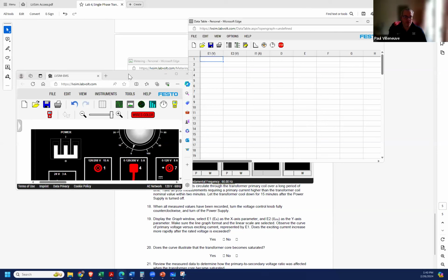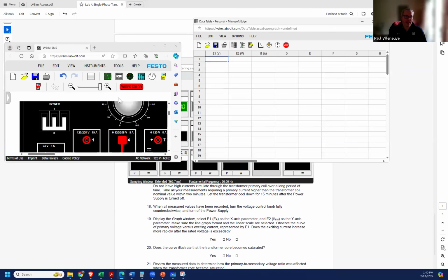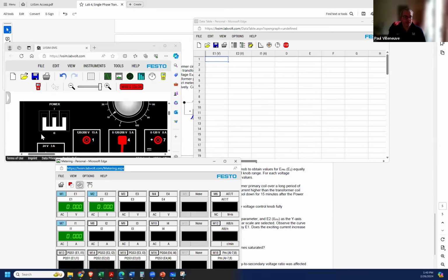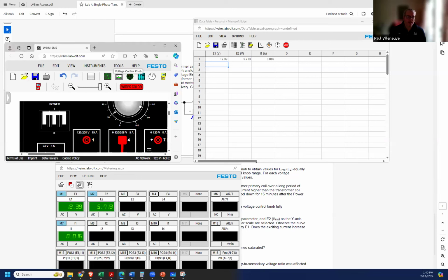The very first point I'm going to take is at 10% voltage—just ballpark, I don't have to be perfect. I'll bring this metering window down here, flip my switch, and record this data point. I've recorded the voltage on both the primary and secondary, as well as the current. Now once it's energized, crank it up to about 20%—again, close enough—and record the data.